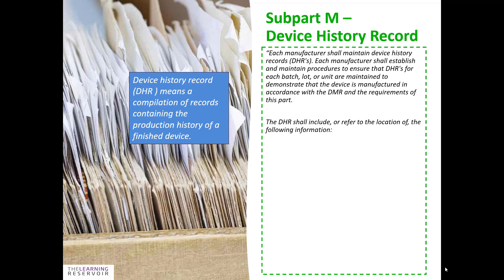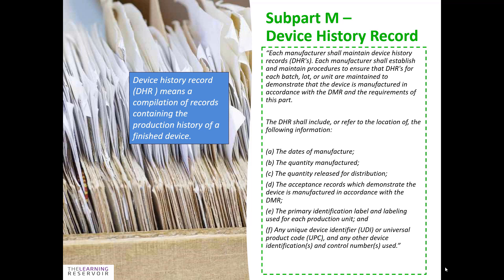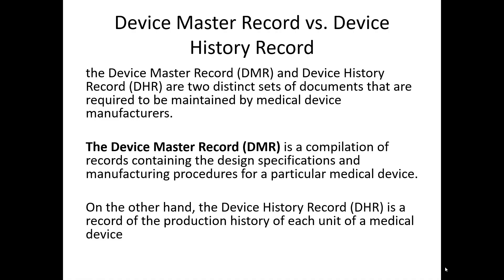The device history record shall include or refer to the location of the following information: the dates of manufacture, the quantity manufactured, the quantity released for distribution, the acceptance records which demonstrate the device is manufactured in accordance with the DMR, the primary identification label and labeling used for each production unit, any unique device identifier or universal product code, and any other device identification and control number used. So all those documents describe how your device was manufactured.